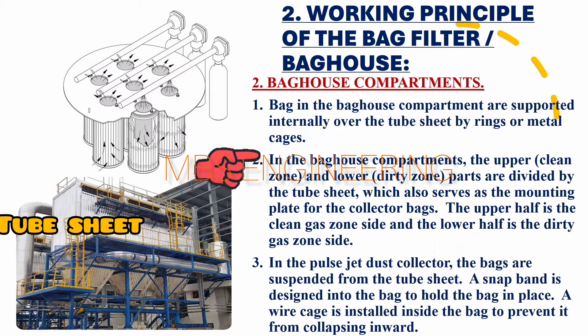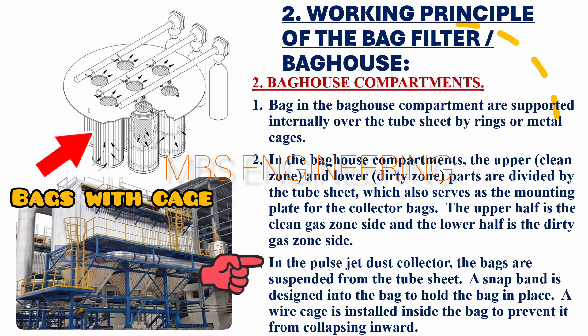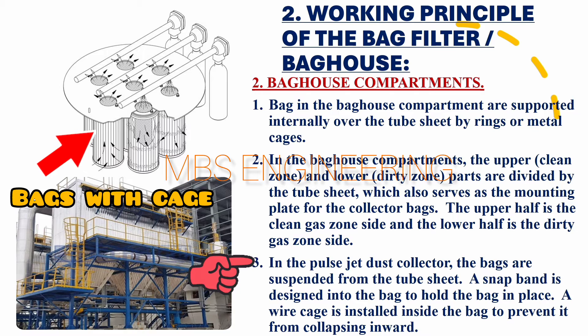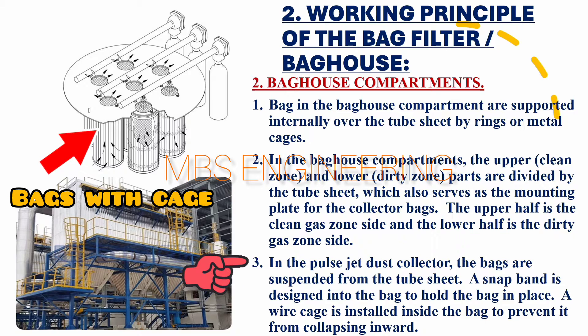In the pulse jet dust collector, the bags are suspended from the tube sheet. A snap band is designed into the bag to hold the bag in place. A wire cage is installed inside the bag to prevent it from collapsing inward.